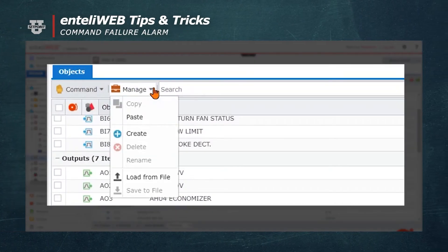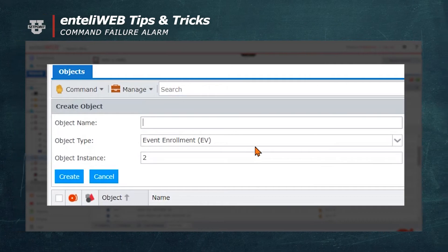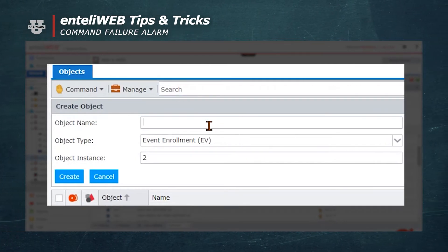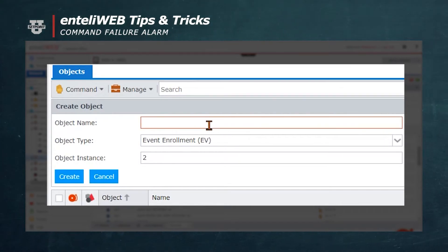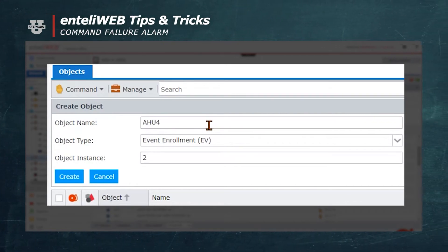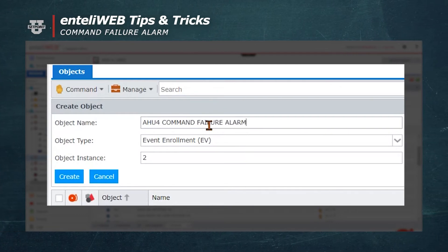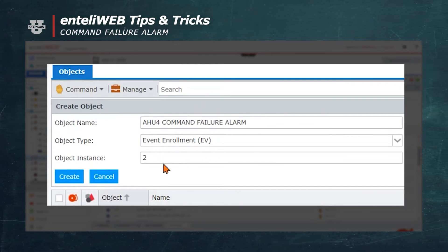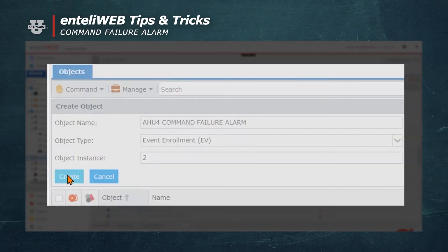To create the command failure alarm, go to Manage then select Create. It's already showing the event or object type — the object type should be EV, or event. In the object name we'll call it AHU4 Command Failure Alarm, which identifies the equipment. Note that the object instance is going to be my second event for this object controller; the system automatically assigns the next available instance number. Now we'll select Create.